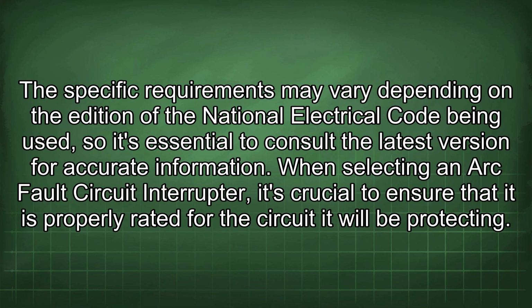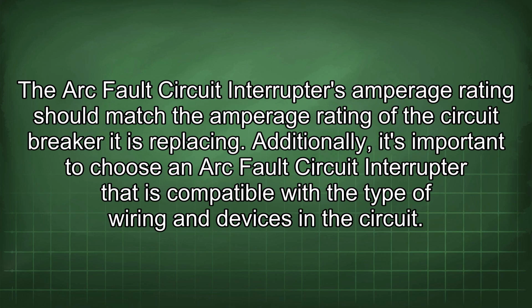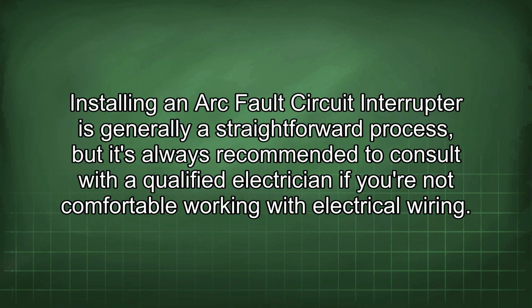When selecting an arc fault circuit interrupter, it's crucial to ensure that it is properly rated for the circuit it will be protecting. The arc fault circuit interrupter's amperage rating should match the amperage rating of the circuit breaker it is replacing. Additionally, it's important to choose an arc fault circuit interrupter that is compatible with the type of wiring and devices in the circuit. Installing an arc fault circuit interrupter is generally a straightforward process, but it's always recommended to consult with a qualified electrician if you're not comfortable working with electrical wiring.